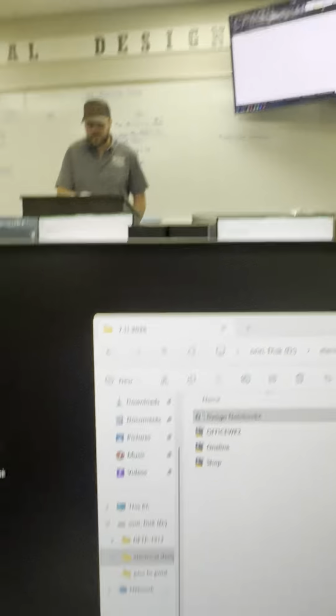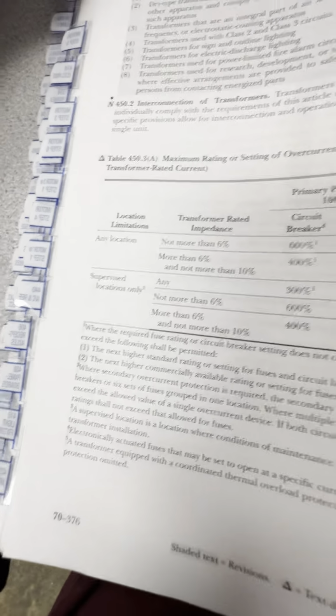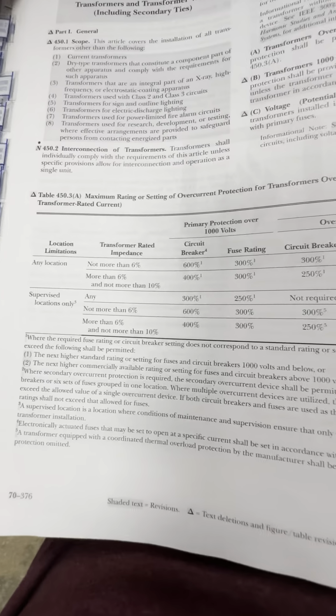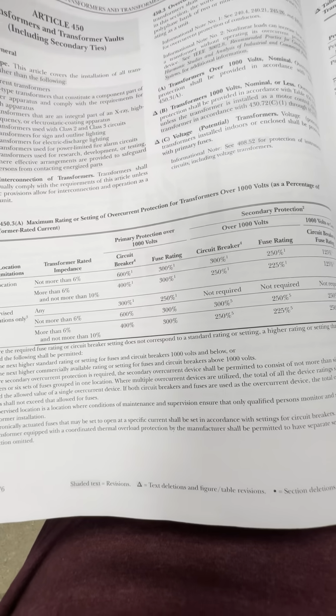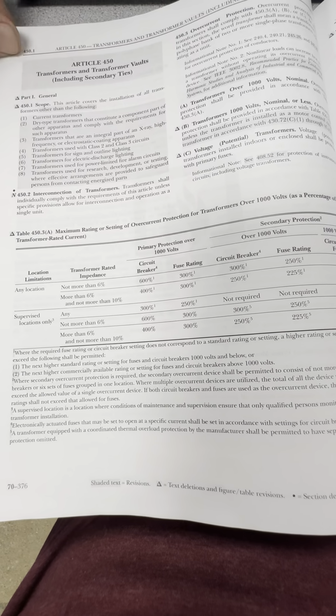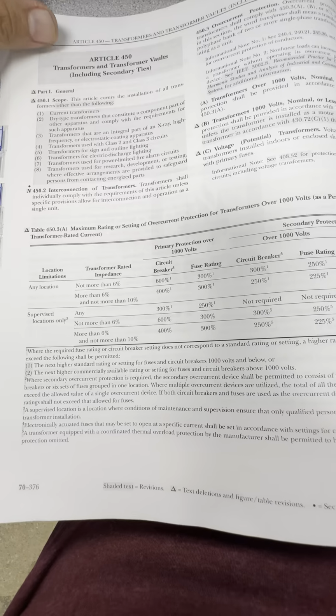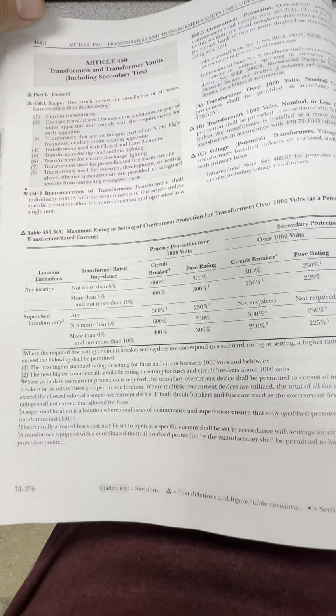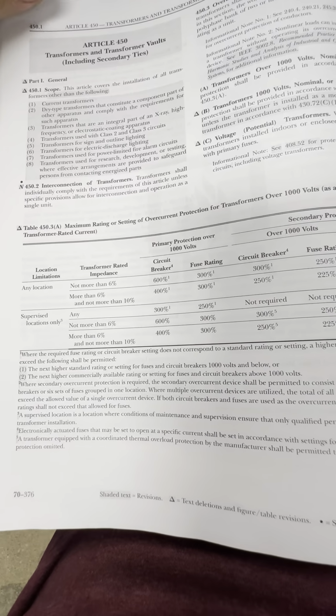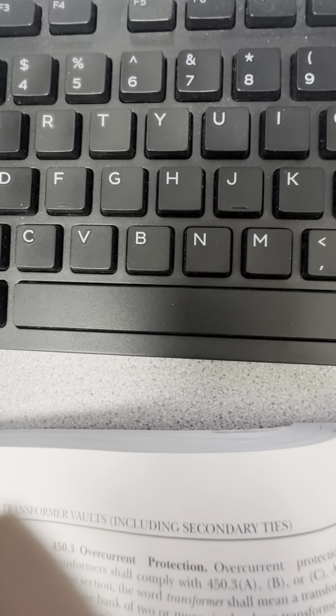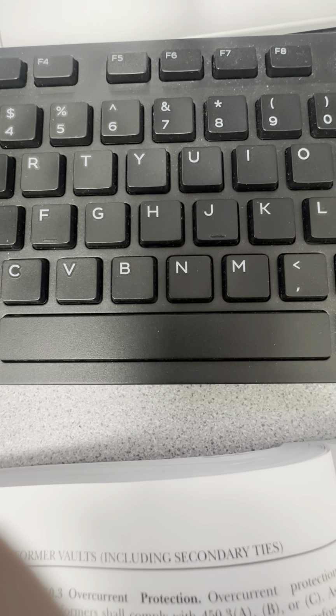So if you notice there's that little subnote 3 next to that. If we go down to the bottom and I read that, it says a supervised location is a location where conditions of maintenance and supervision ensure that only qualified personnel monitor and service the transformer installation. So since our facility is a 24/7, 365 operation, we're going to say that all of our maintenance guys are qualified techs to work in there. So we fall underneath that supervised location. So now we're just looking at that bottom half of the table there.